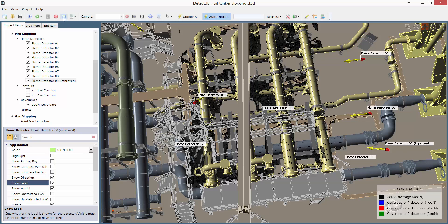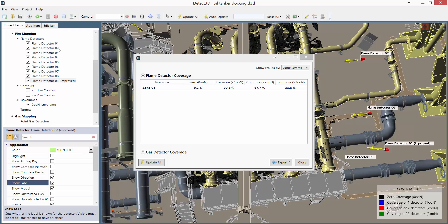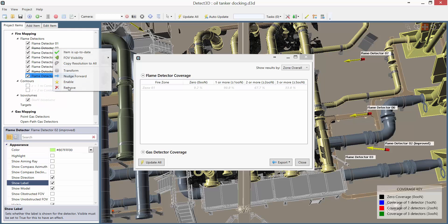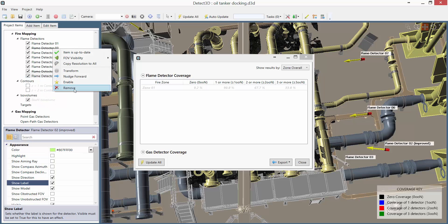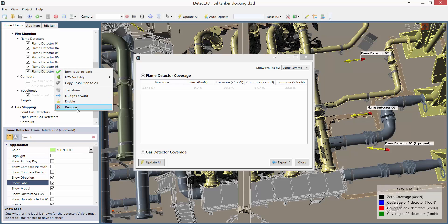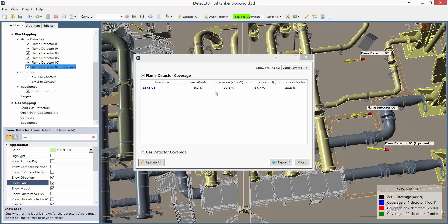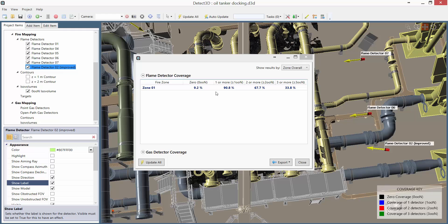If I take a look at the new coverage results for the zone, I can see that I do have greater than 90% coverage by one or more detectors. And this is a pretty significant result. I can just delete all the detectors that I switched off to get the final layout. And what I'm left with is coverage that exceeds my performance criteria of 90% one or more coverage, and say 50% two or more.